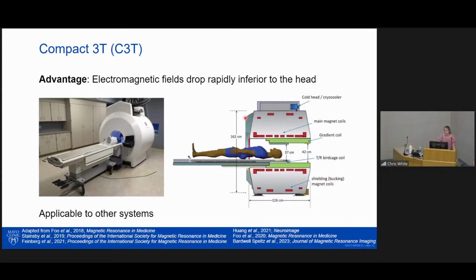So because of the smaller scanner size of the compact 3T, the patient is only partially inserted into the scanner bore. A major advantage of the compact 3T for patients with implanted devices is the electromagnetic fields drop off rapidly inferior to the head due to that smaller scanner size. Therefore, devices could be safely scanned at their location even if the labeled MR conditions are exceeded at the location of the imaged anatomy. So, for example, let's say this subject had a spinal cord stimulator located in the lumbar region or at the yellow star location on this figure. We may be able to perform a brain exam of this subject since the electromagnetic fields drop off rapidly between those 2 star locations. This is the only compact 3T in existence.